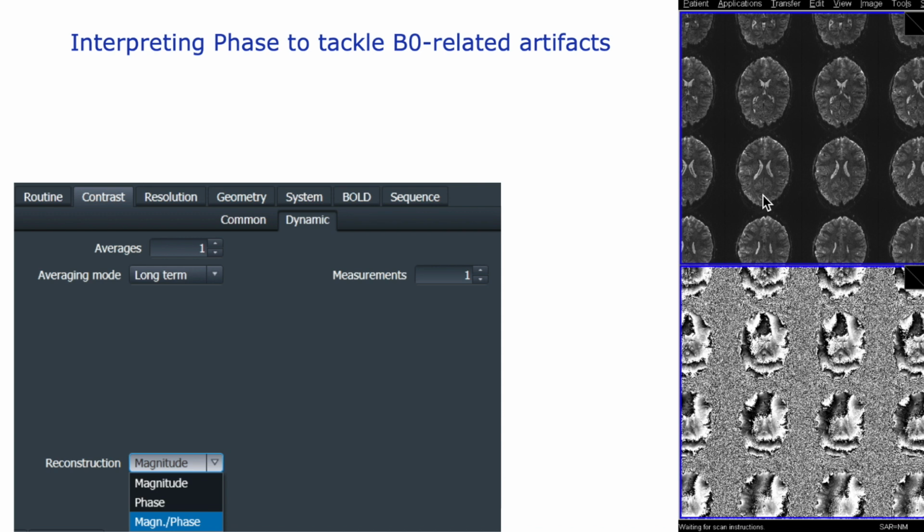You don't clearly see this in the individual images of the magnitude time series, but especially as soon as you run offline tSNR, you can see inhomogeneity problems there, especially phase inconsistencies that change with very small field drifts. There are a few things that you can do about it as soon as you detect those. One very effective way that is super easy is just switching the phase encoding direction. Sometimes the artifacts just move somewhere else. The inhomogeneity, of course, is still the same, but the artifacts manifest in a different way.